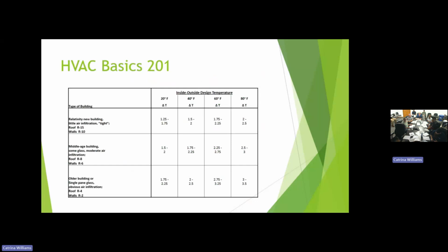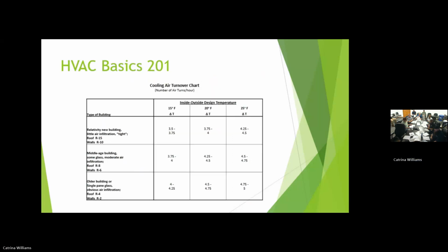But at the cooling unit now, well, it's a whole new ball game. Again, cooling or cold air is harder to move. Now we're talking up to 5 turns an hour. Here's the good news. Doug and I have said on heating, hot air rises, so we have to figure the volume from the floor to the ceiling. On cooling, you figure the volume from the floor to the top of the unit. So that'll help get this 5 turns per hour.